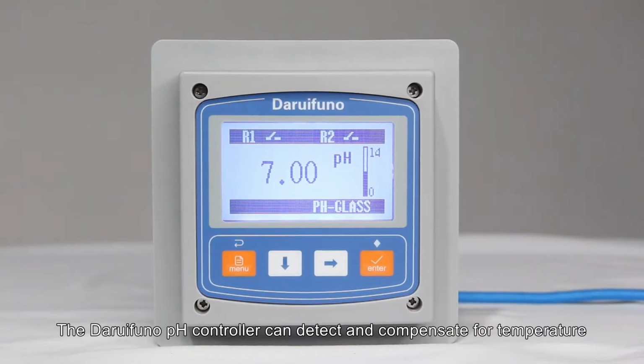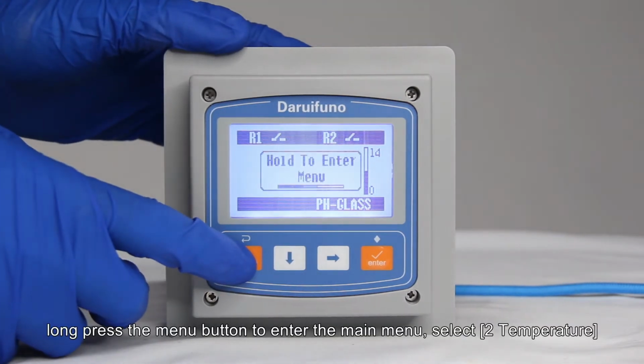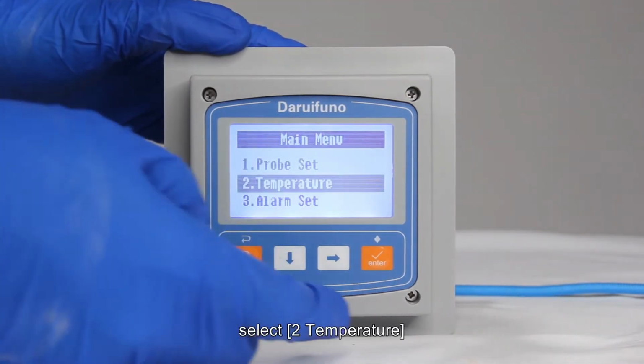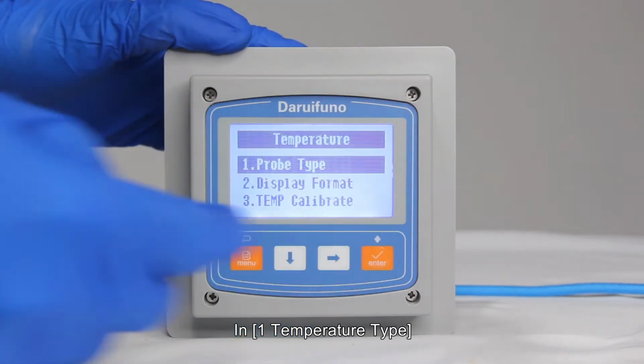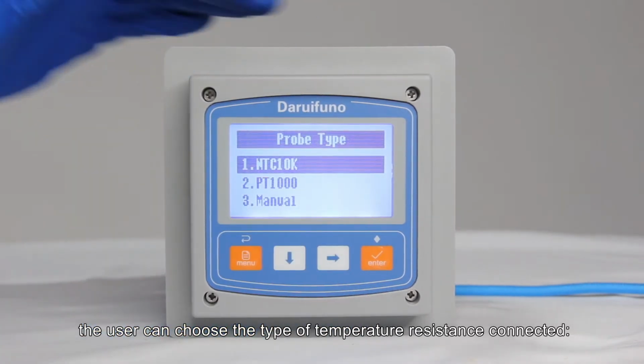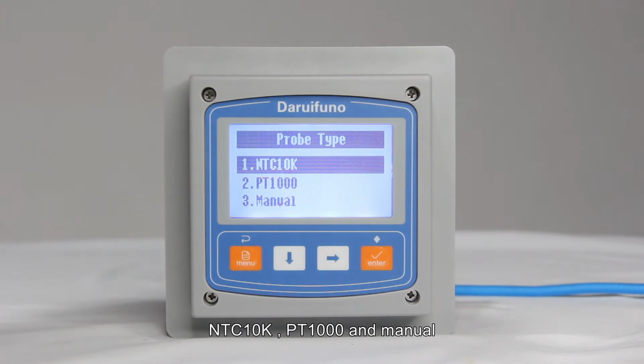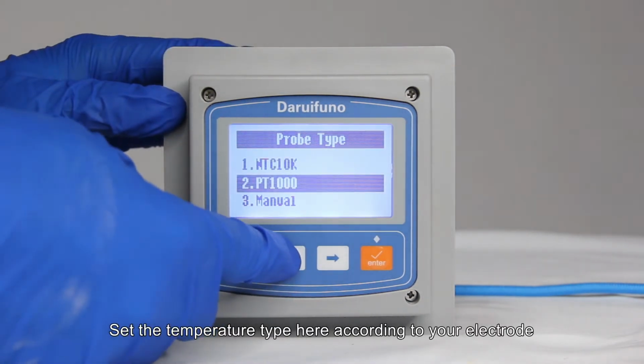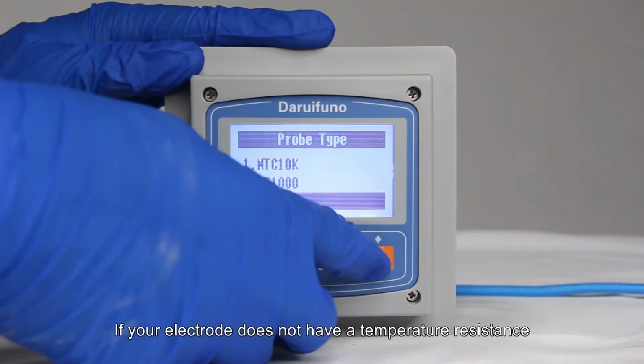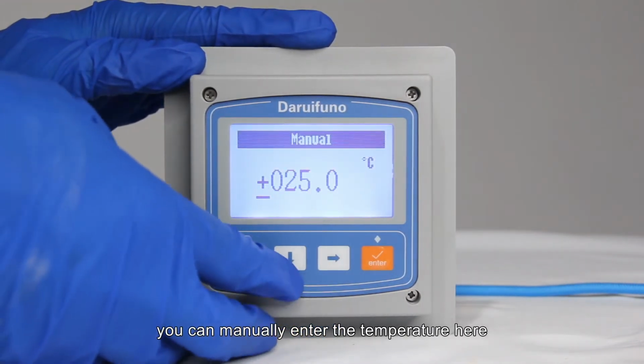The Daruifuno pH controller can detect and compensate for temperature. First, long press the menu button to enter the main menu. Select 2, temperature. In 1, temperature type, the user can choose the type of temperature resistance connected: NTC10K, PT1000 and manual. Set the temperature type here according to your electrode. If your electrode does not have a temperature resistance, you can manually enter the temperature here.